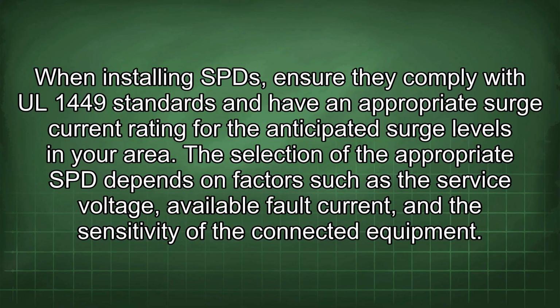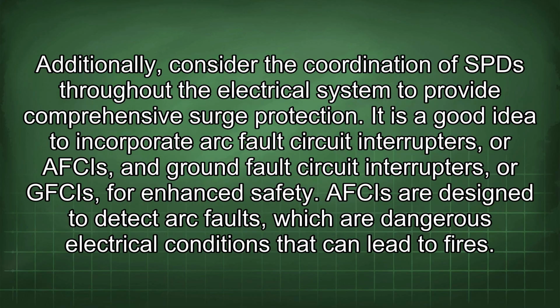When installing SPDs, ensure they comply with UL 1449 standards and have an appropriate surge current rating for the anticipated surge levels in your area. The selection of the appropriate SPD depends on factors such as the service voltage, available fault current, and the sensitivity of the connected equipment. Additionally, consider the coordination of SPDs throughout the electrical system to provide comprehensive surge protection.